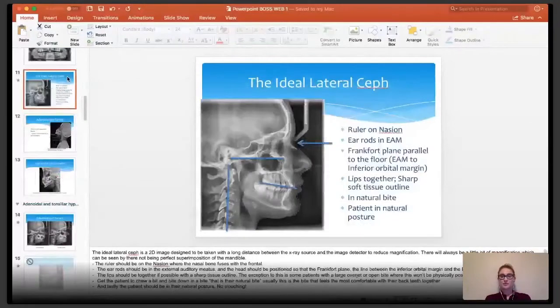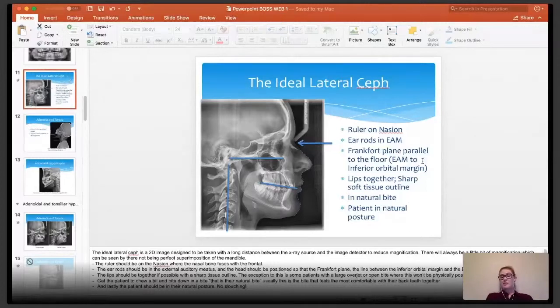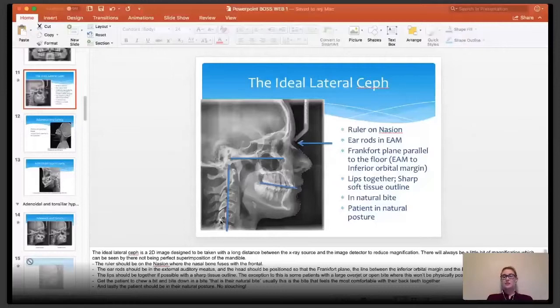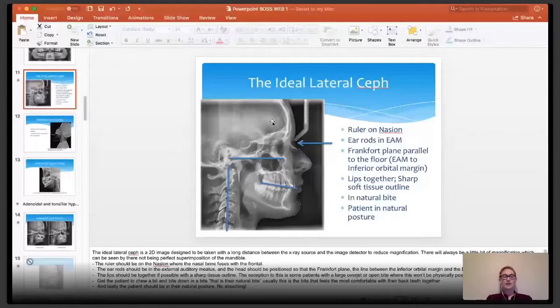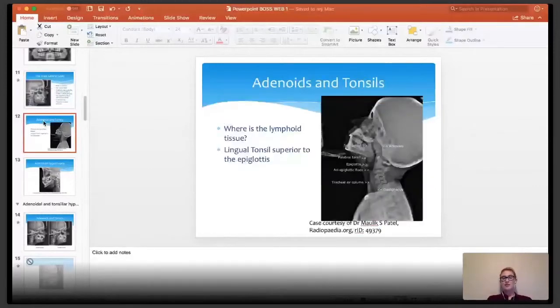When looking at your ideal lateral ceph, the ruler should be on nasion and the ear rods in the ear hole. Your Frankfurt plane — the external auditory meatus to the inferior orbital margin — should be parallel to the floor. The patient should be in their natural posture, looking as far ahead into the distance as possible, in their natural bite with lips together and relaxed. This is important not just for cephalometric tracings but also to make it easy to compare cephs against one another in the future.